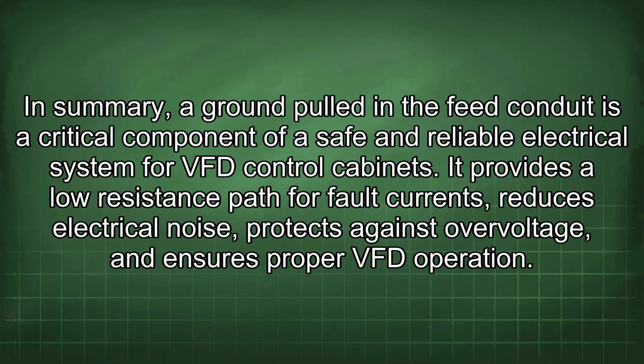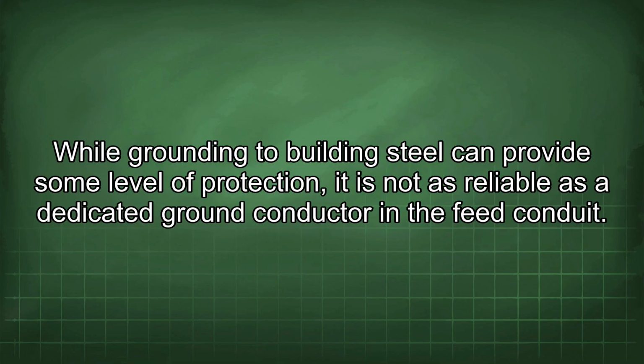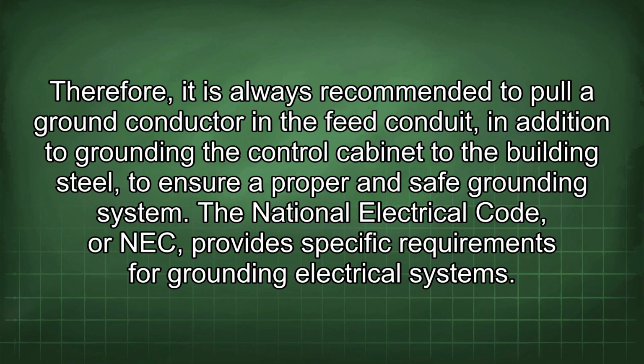In summary, a ground pulled in the feed conduit is a critical component of a safe and reliable electrical system for VFD control cabinets. It provides a low resistance path for fault current, reduces electrical noise, protects against overvoltage, and ensures proper VFD operation. While grounding to building steel can provide some level of protection, it is not as reliable as a dedicated ground conductor in the feed conduit. Therefore, it is always recommended to pull a ground conductor in the feed conduit, in addition to grounding the control cabinet to the building steel, to ensure a proper and safe grounding system.